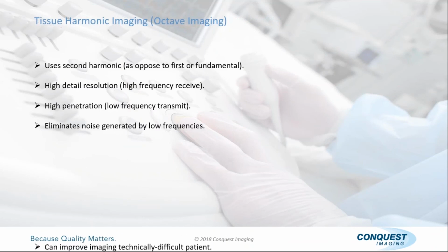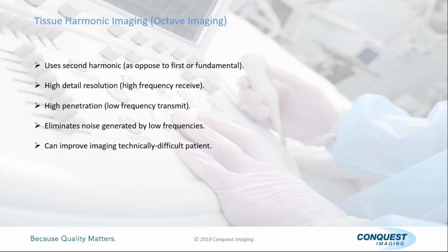Harmonic imaging. This is for the technically difficult patients, and technically difficult is really defined as obese, okay, hard to scan. So what do we have to do? One of the principles of ultrasound is we need a low-frequency probe to penetrate a long way, but a low-frequency probe gives us poor resolution, so we don't get a good picture. Well, if we have a technically difficult patient, we have to sacrifice image quality for the penetration capability. Harmonic imaging kind of does the best of both worlds. We transmit at a low frequency and receive at a higher frequency. So it transmits at 1 and receives at twice the transmit frequency. So it helps us improve our image.